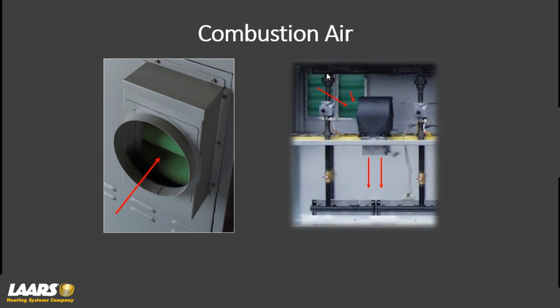Now, also in the past, we've seen a lot of jobs out there in the middle of the winter, an install for a building, and they need temporary heat. A lot of times they'll take the front cover off the boiler. What happens? We're no longer filtering the air. So all of that construction dust is coming right in the front of the boiler, into the blower, down into your blower deck, and below your blower deck, and into your burners. So keep that in mind. If you're running these boilers, that front cover needs to be on so we can filter the air.